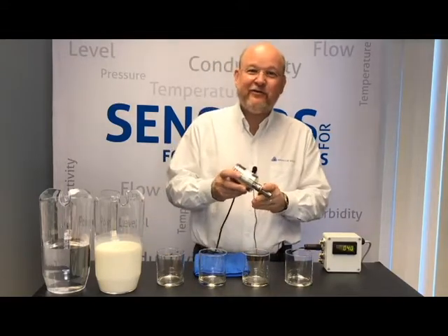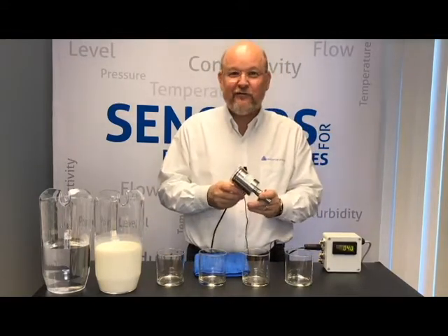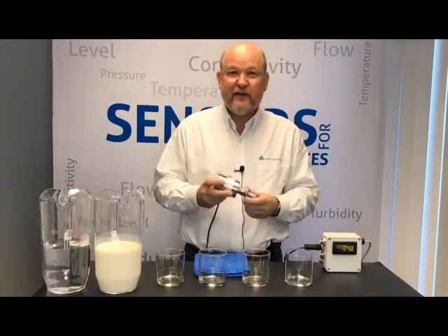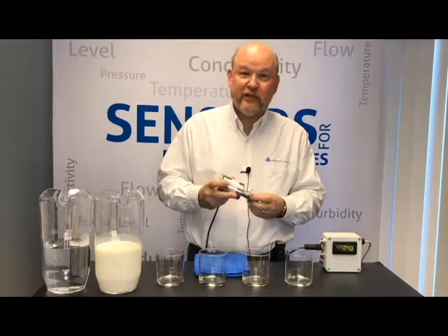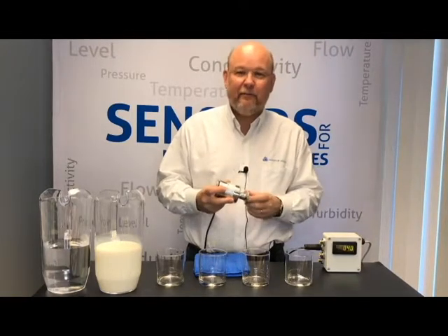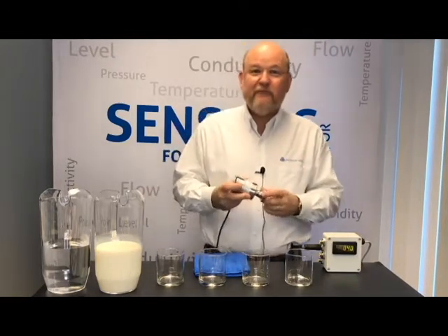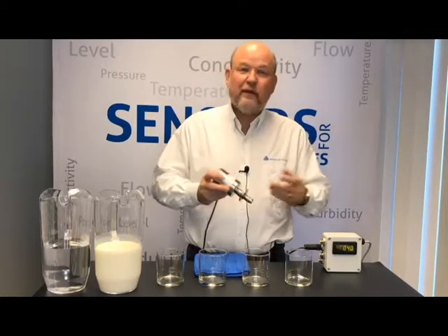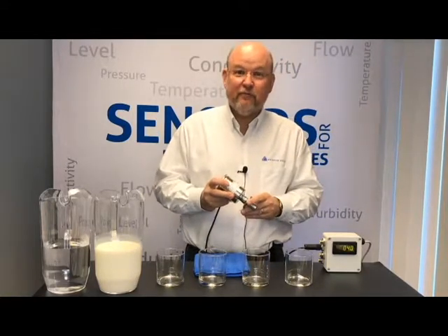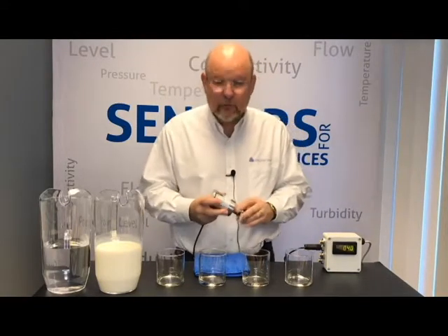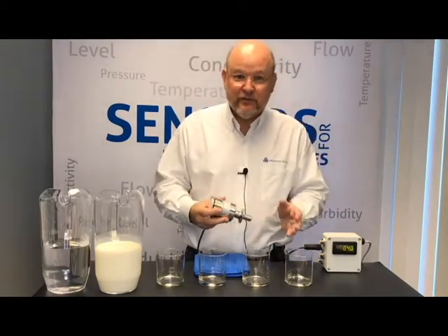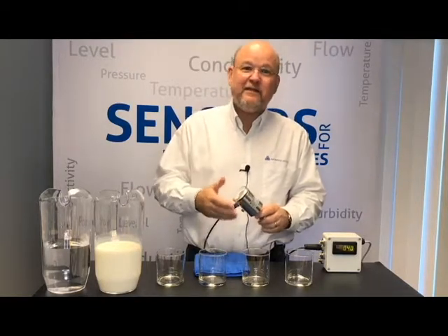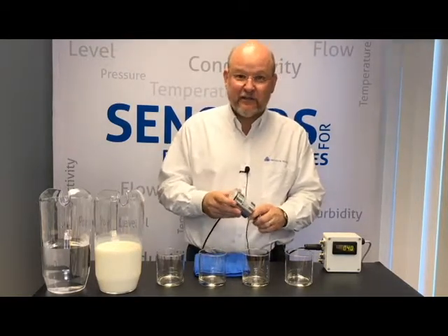This is a backscatter turbidity sensor that we launched earlier this year and is used in applications for product phase transition, typically water flushes pushing out product through a plant. With that in mind, oftentimes I'm asked the question, how does an ITM 51 really relate to the product that's moving through my plant?